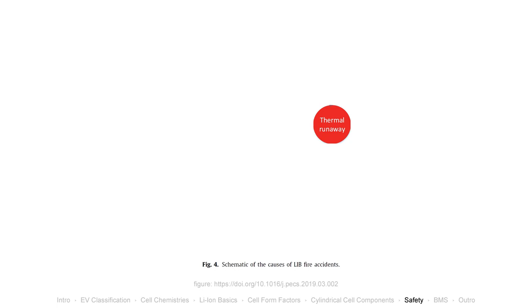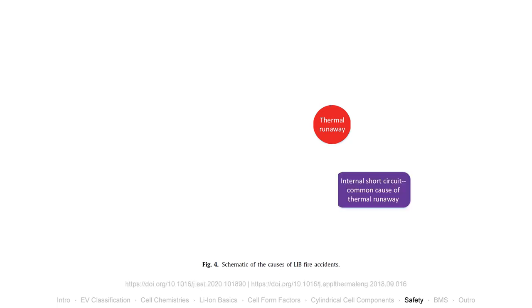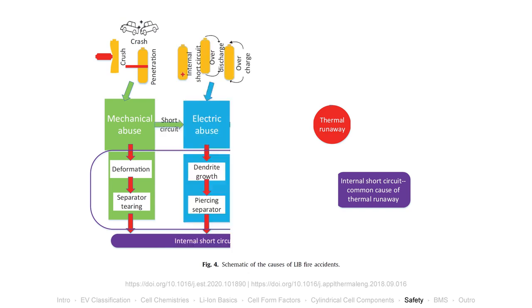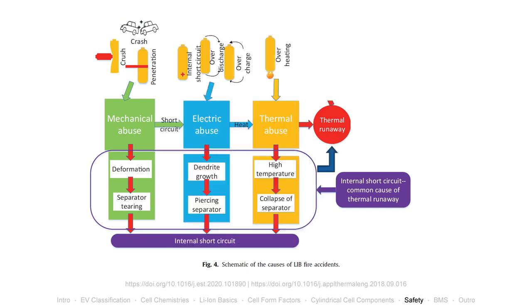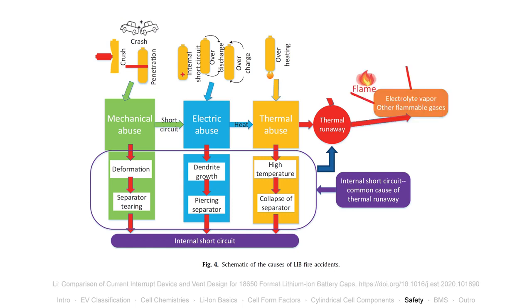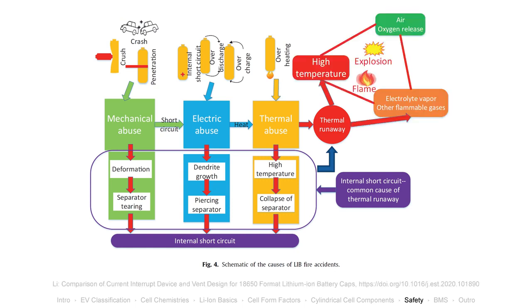Triggers for thermal runaway are either manufacturing defects like internal short circuits or abuse, which is operation outside of a cell's specification. There are mechanical, electrical, and thermal types of abuses. The effects of thermal runaway are the venting of flammable gases which may ignite, and the emission of heat which may trigger thermal runaway in nearby cells, causing a thermal runaway cascade in the whole battery.